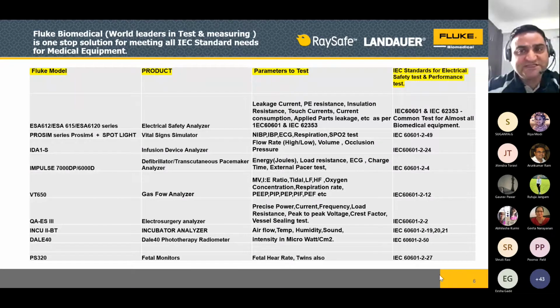Let me tell you, IEC 60601 is mainly designed for manufacturers who are designing or producing equipment, like Philips, GE. They normally use IEC 60601. And when it comes to field services or at a hospital, suppose you are a biomedical engineer working in some hospital, you can use IEC 62353 because you need not do everything from top to bottom, like in IEC 60601. So you need to do 4 to 5 vital things to ensure that your equipment is safe for patient use.